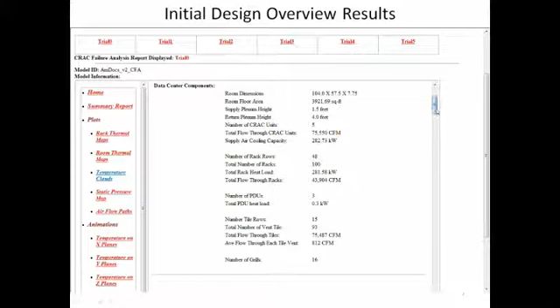But again, the reason that they were doing that from an operations perspective was because in a failure mode, they had too high of an escalation of supply inlet temperature. So they were trying to keep it at the lower end of that threshold, around 68 degrees.